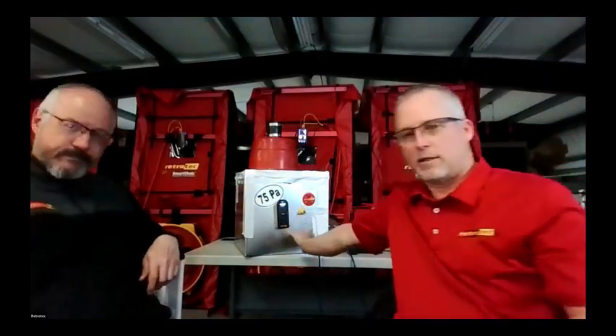It is a single channel manometer. It is inexpensive but high precision unit. It has the circular screen on it, which rotates with your orientation. It's got a belt clip on the back that is also magnetic. It's got two buttons, the power button and the menu button. By pressing the menu button, you can toggle through your different metrics of output, being PSF, millibars, PSI, pascals, or inches of water. If you hold the menu button, it'll take you to a screen where you can do time averaging, or you can set it to timeout and turn the screen off after a certain time.